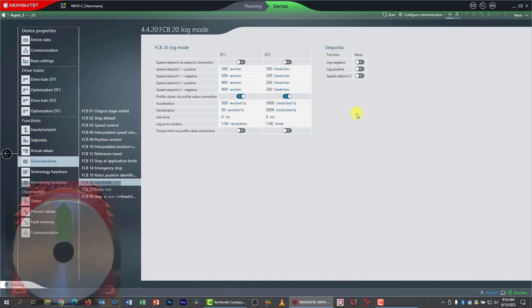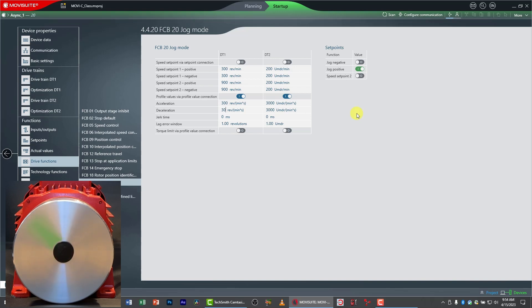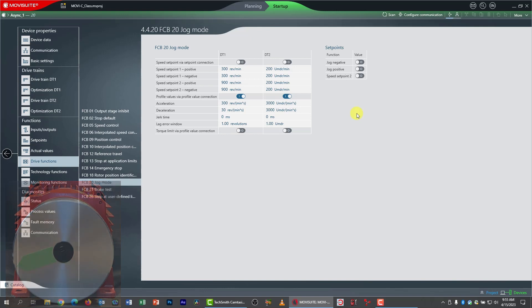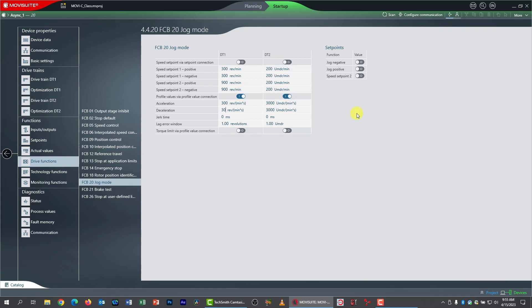Let's test jog mode. I'll remove controller inhibit on DI00, activate jog mode with DI01, pick a direction with DI02 or DI03, and use DI04 to select between the two jog speeds. I tried both clockwise and counterclockwise at the lower speed, then switched to the higher speed with DI04 — but I'm not seeing any real difference in ramp behavior. Your lab instructions ask: does the drive's behavior reflect the ramp settings? The answer is no. We're getting basically one ramp speed all the time. Why?